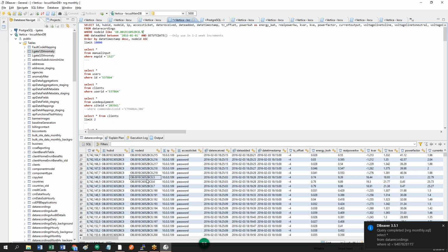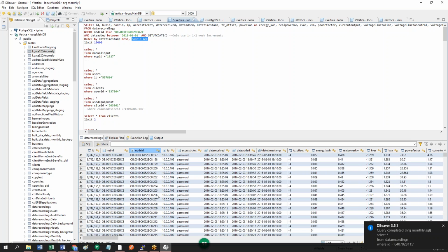If you run it with this percentage sign, and this is why I have this node ascending, it orders it 5, 6, 7, and then 190 through whatever. So let's say the guy on site doesn't have a computer or his computer died or whatever, and he's saying, oh, it's saying an error, and they were named just inverters. If you looked in the database and the thing was online, you would see, let's say 190, 191, 192, and then 194. You could say, oh, 193 is not responding. Maybe you forgot to program it. So he could go over to the inverter and be like, yep, I didn't change the baud rate, or I didn't program it at 193. So you can make that change, and then the next upload, you happen to see it.